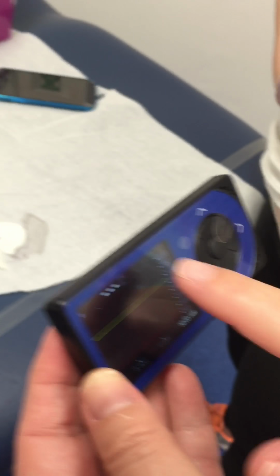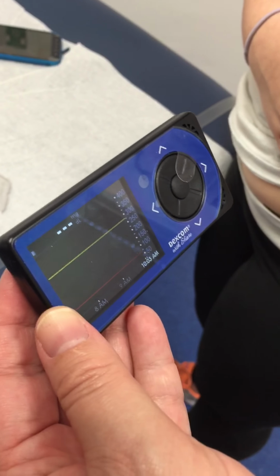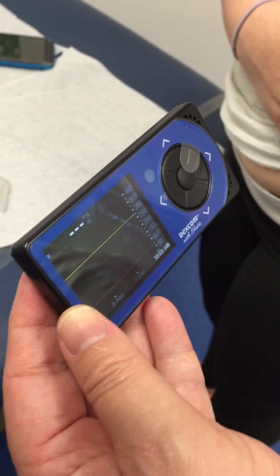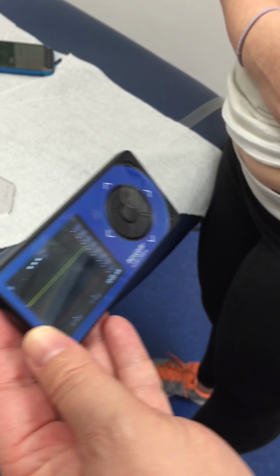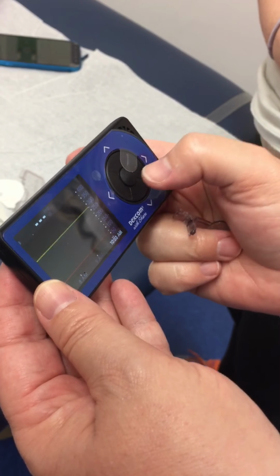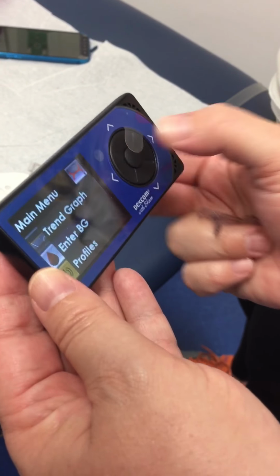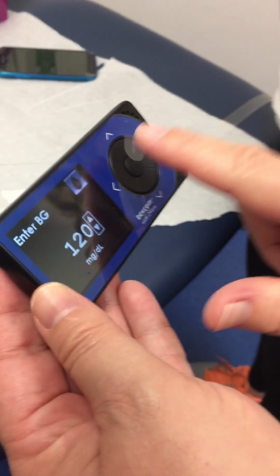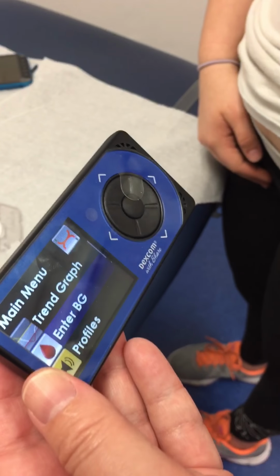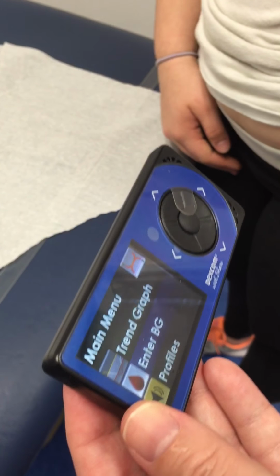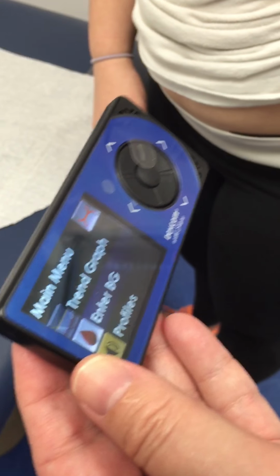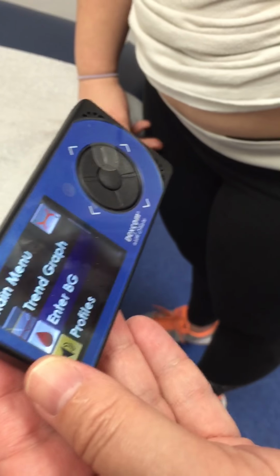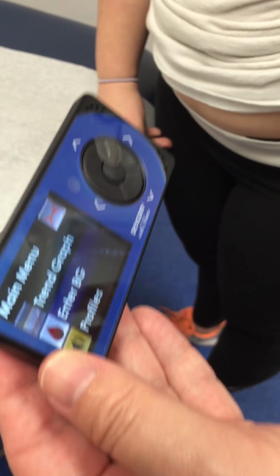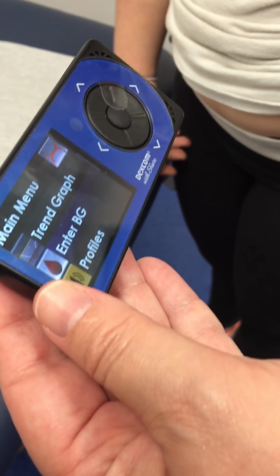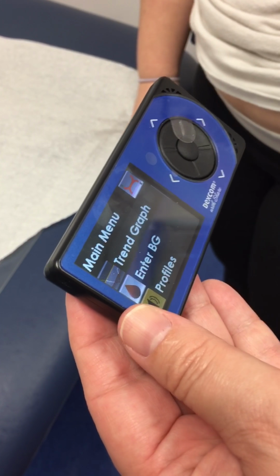Okay, and so you see you've got this little green circle. In 2 hours, that little green circle is going to be filled in all the way. It should show you 2 drops of blood. Okay, that's going to be your first time to do calibration, okay? So that means you're going to prick your finger, you're going to get a blood sugar, and you're going to enter it in. I'm going to show you how to do that. So you hit that center button, enter BG, and you scroll up and down to whatever your BG is at the time and center to enter, okay? For the very first time after you change, when you put on a new site, you have to calibrate it twice in a row. So that very first time in 2 hours, when you see those drops, 2 drops of blood, you've got to enter a blood sugar, and then you've got to test again right behind that and enter it again, okay? That's the only time you have to test twice in a row and put it in, is right after you put on a new site, okay?